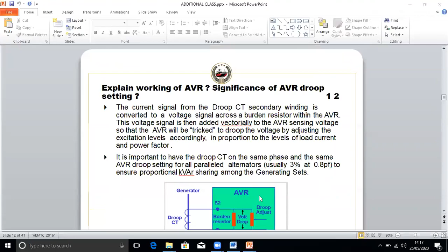This is the droop of the AVR. This is called the droop CT, the droop current transformer. The current signal from the droop CT winding, this is the primary, is converted into a voltage. Why? Because this burden resistor is there. It is converting the current into voltage. That is why you have a burden resistor.